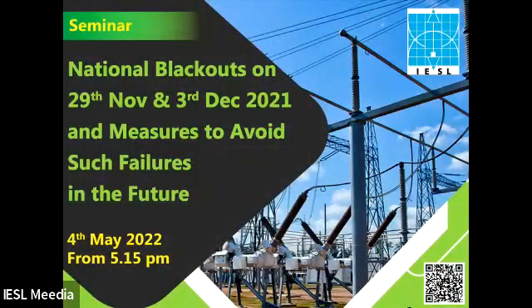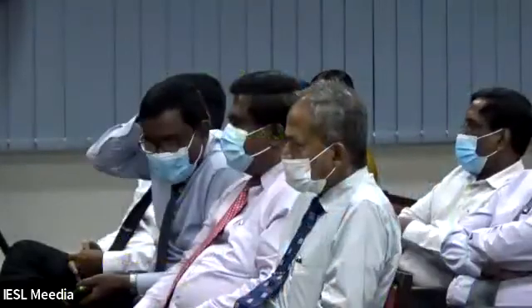Why CEB did not take care of those in the early stages, for protection, correct earth fault settings, and not paying attention to the November incident. With regard to the incorrect setting, the question raised by Mr. Jagat, I think during our presentation we have explained that the earth fault settings, as per our standard settings, were implemented in the 220 kV Biyagama-Kothmale line, and with the settings that we adopted, the relay properly operated and tripped the line in 22 seconds.